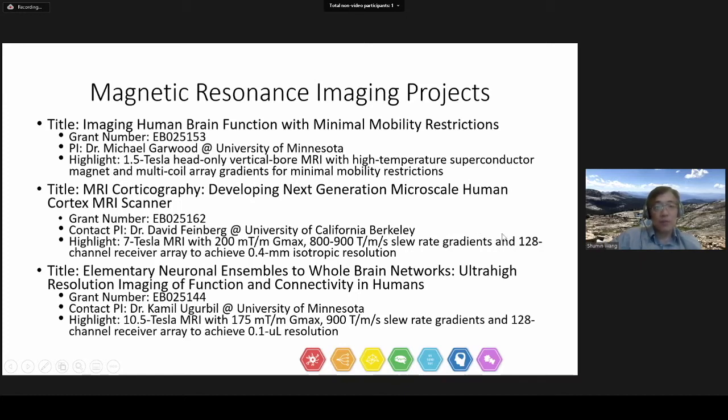Dr. David Feinberg from the University of California, Berkeley proposed to develop very powerful, fast resonant imaging gradients, which feature around 800 to 900 tesla per meter per second slew rate and 128-channel receiver array to achieve 400 micron isotropic resolution for 7 Tesla functional imaging. Dr. Ugurbil from the University of Minnesota also proposed to further develop their 10.5 Tesla MR scanner with very fast gradients featuring 900 tesla per meter per second slew rate and 128-channel receiver array, with a goal to achieve 0.1 microliter resolution, which is about 400 to 500 micron isotropic.